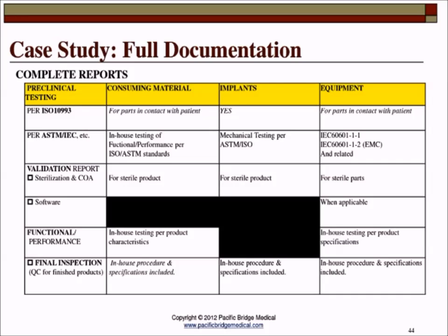As mentioned before, for materials, the in-house testing by following the international standards can be referred to as the functional test reports. And then the mechanical testing for implants can be considered the functional test reports as well. Now, for equipment, in-house testing, according to the product specification that you claim, should also be provided, such as the wavelength for lasers and the frequency for RF equipment, and then input, output, power, etc. for the electric equipment should be provided.